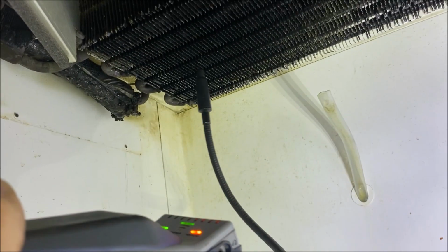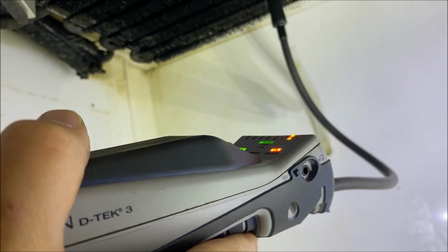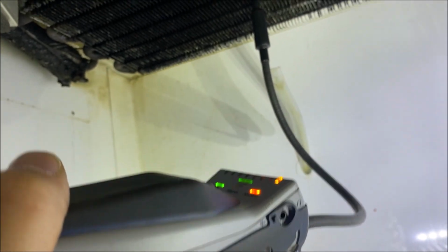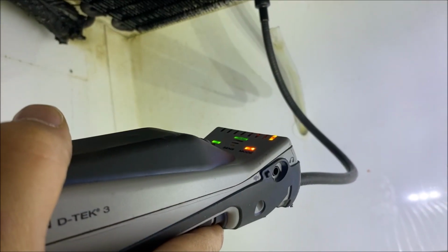We can braze them back up. So that is an option at the moment. But remember, we had a leak on the right-hand side of the evaporator pan. And look at that, we have a leak in the coil. This coil is no longer repairable.